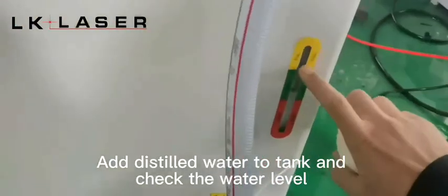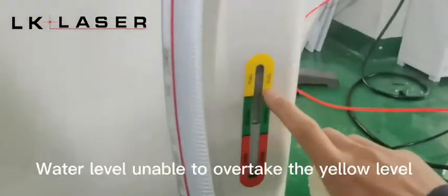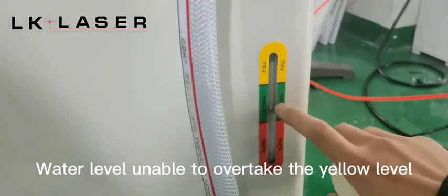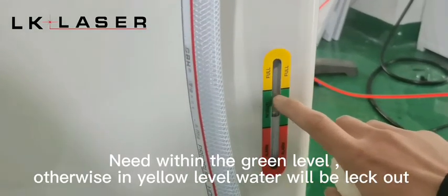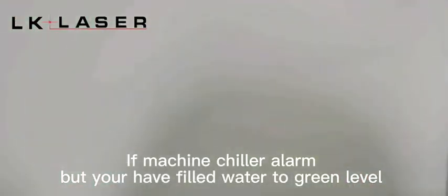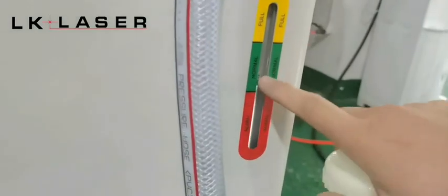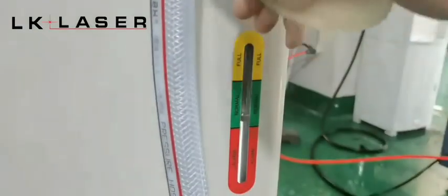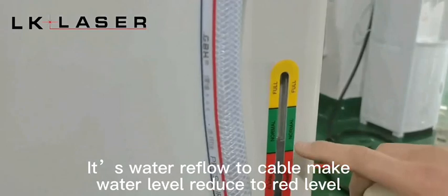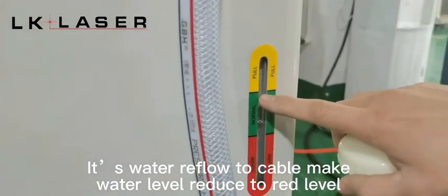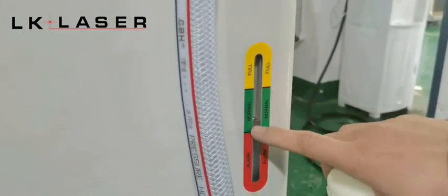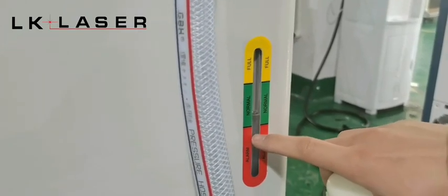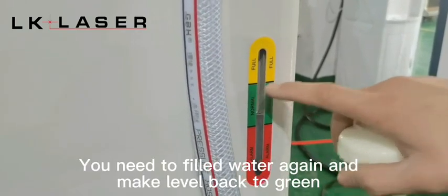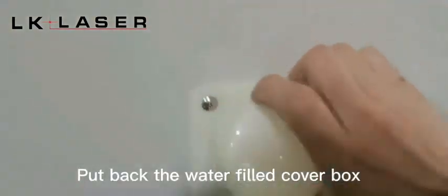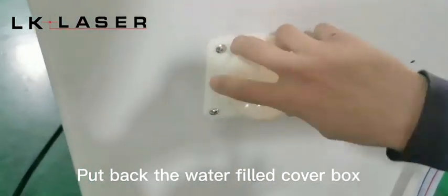Add distilled water to the tank and check the water level. The water level is unable to overtake the yellow level. It needs to be within the green level, otherwise at the yellow level water will be let out. If the machine chiller alarms but you have filled water to the green level, it is water reflowing to the cable, making the water level reduce to the red level. You need to fill the water again and make the level back to green. Put back the water-filled cover box.